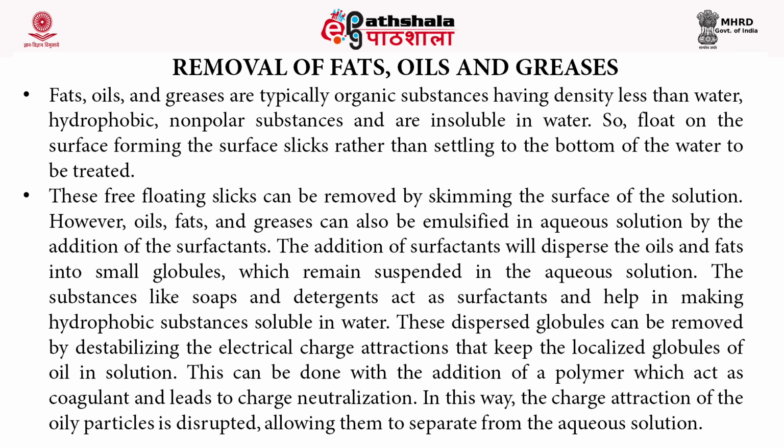These dispersed globules can be removed by destabilizing the electric charge attraction that keeps the localized globules of oil in solution. This can be done with the addition of a polymer which acts as a coagulant and leads to charge neutralization. In this way, the charge attraction of the oily particles is disturbed and it allows them to separate out from the aqueous solution.